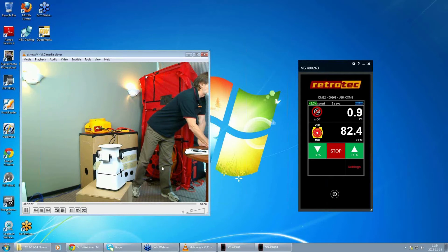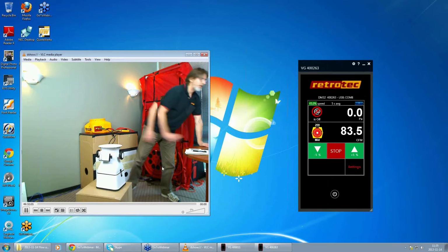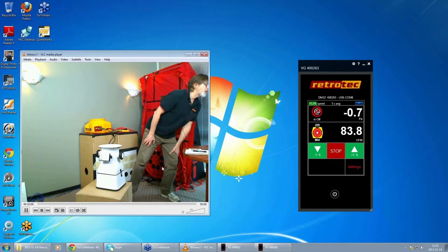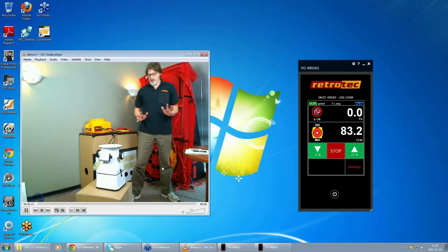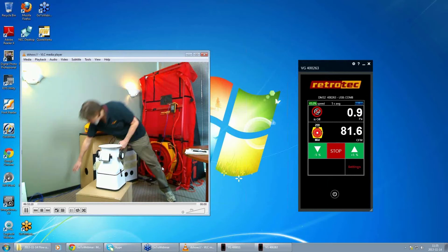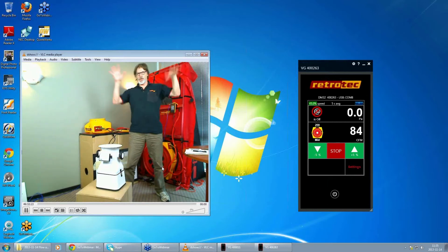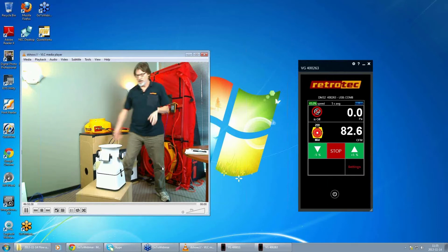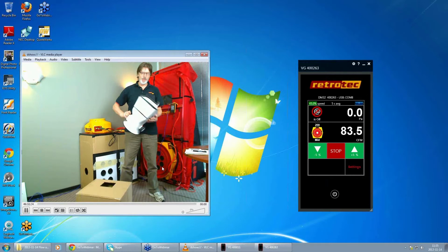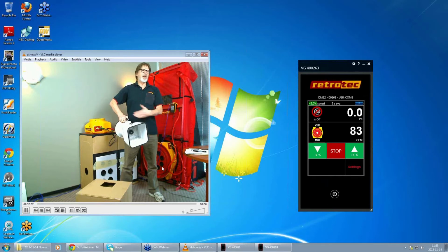So Peter was asking why it works on a return but not on a supply. The reason it doesn't work on a supply is because of the jetting effect that comes out. There's a huge amount of turbulence which comes out of this hole when the air is flowing at it, so the pressure jumps around all over the place. So you'll always get good readings on returns but never supply because of the jetting effect. What this device does for jetting is it has a special chamber in there that neutralizes all of that in the front section of the flow finder, and then it measures the flow in the back end. In every other device on the market, the flow measurement and the pressure neutralization and stabilization are in the same area. What they've done is separate it into two areas, and that's why this thing works so well.